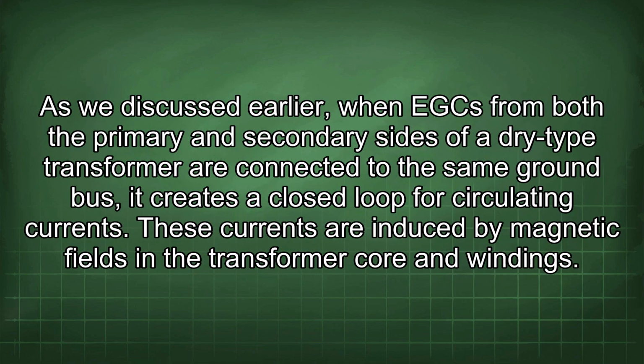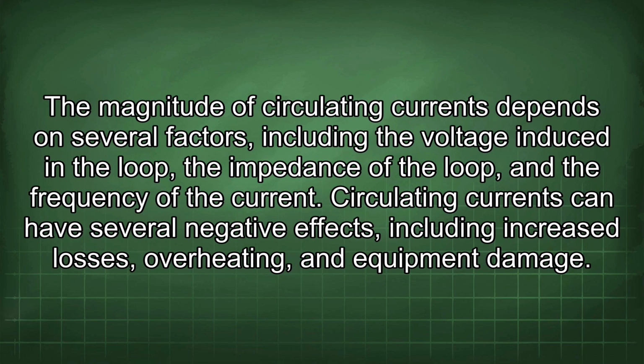As we discussed earlier, when EGCs from both the primary and secondary sides of a dry-type transformer are connected to the same ground bus, it creates a closed loop for circulating currents. These currents are induced by magnetic fields in the transformer core and windings. The magnitude of circulating currents depends on several factors, including the voltage induced in a loop, the impedance of the loop, and the frequency of the current.